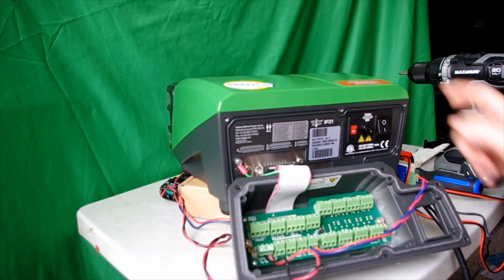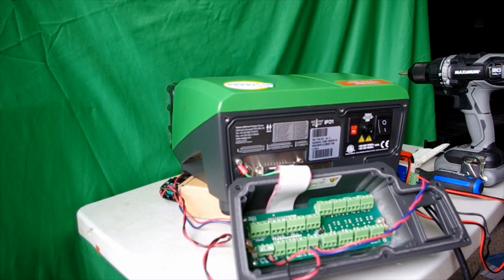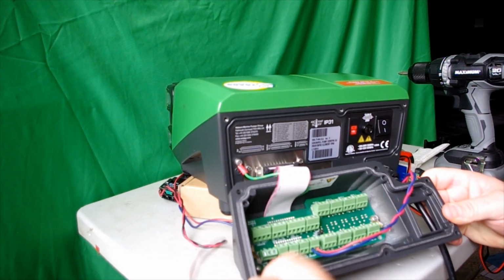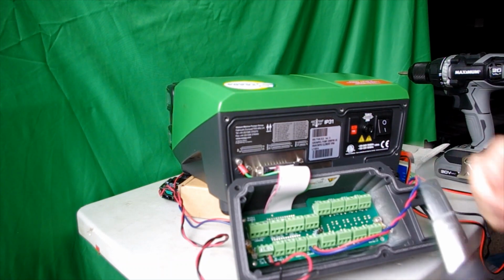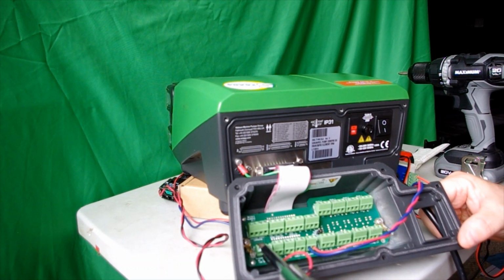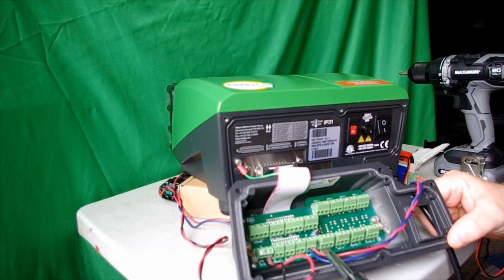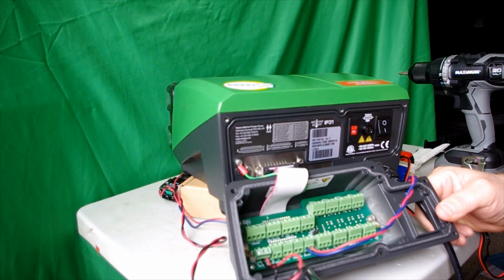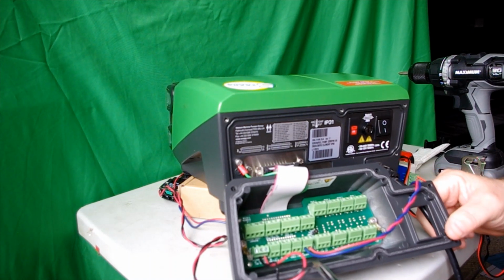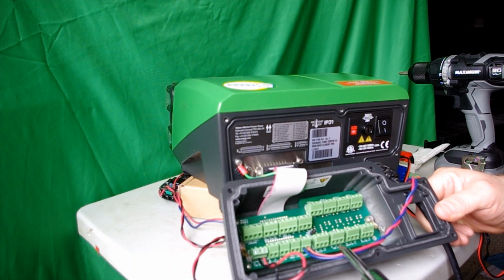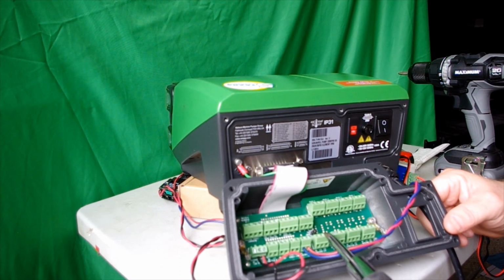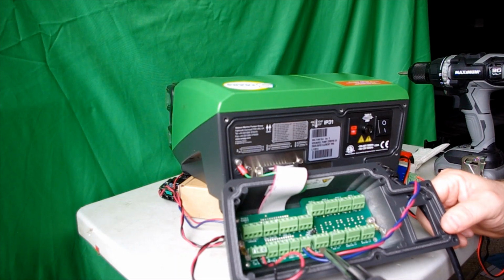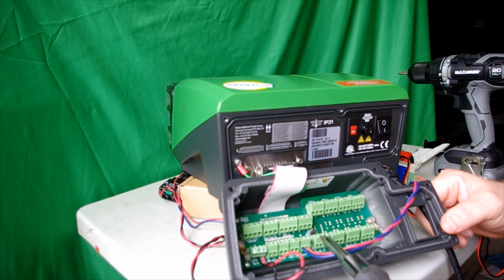So the pump is in the off position, and as you can see, this is our NEMA module. Right now I currently have on the J9 a leak detector wired. On the J5, I have the analog control wired. And what I'm looking for now is the run stop. Auto manual, no. Where are we? Run stop. This is the terminal block you're going to be working with. When you're running the run stop, you would give it a stop signal and a run signal, and that would be done by contact closure.